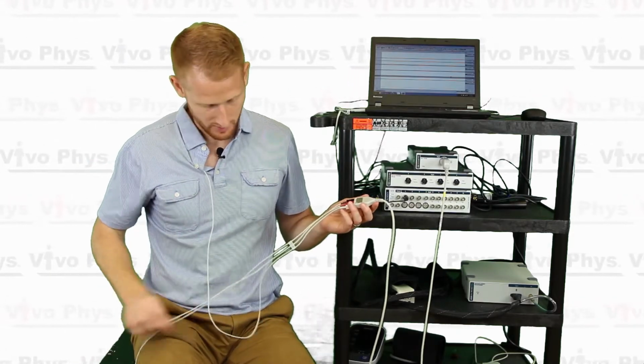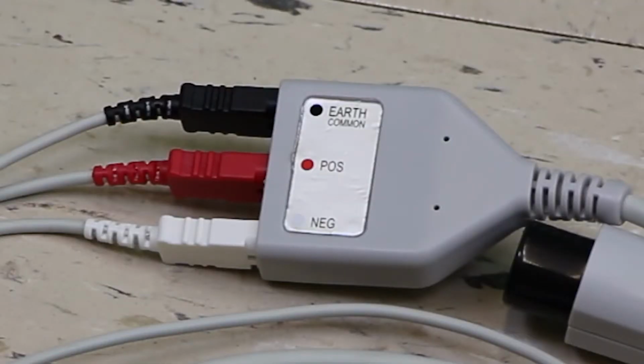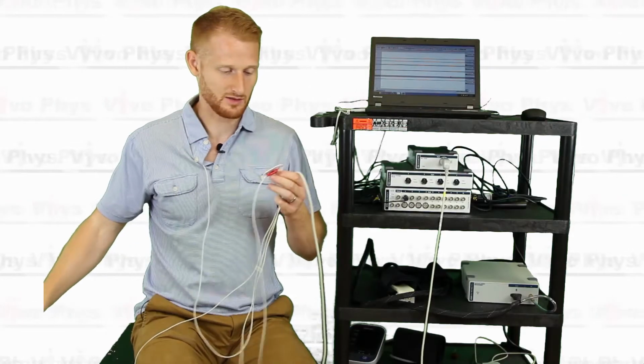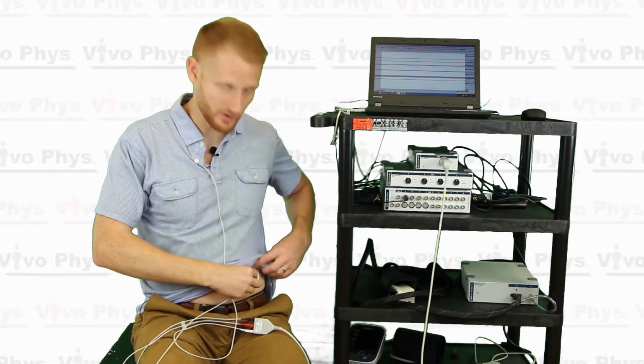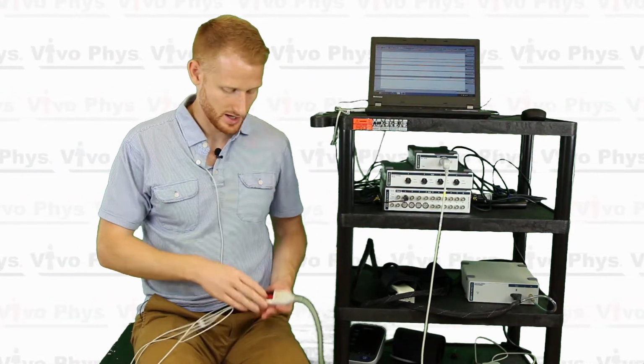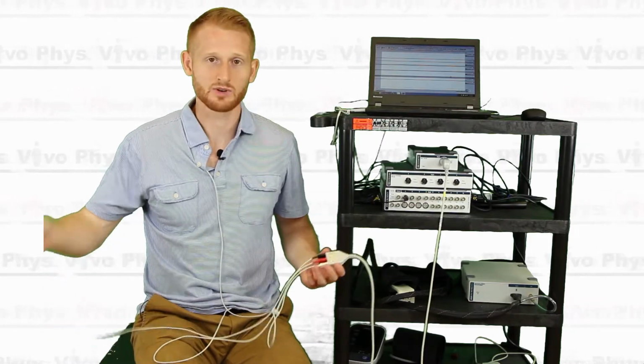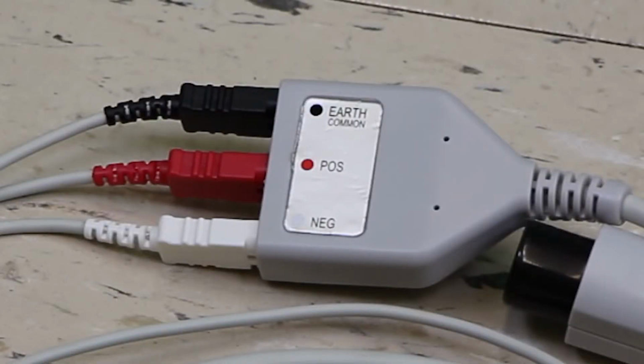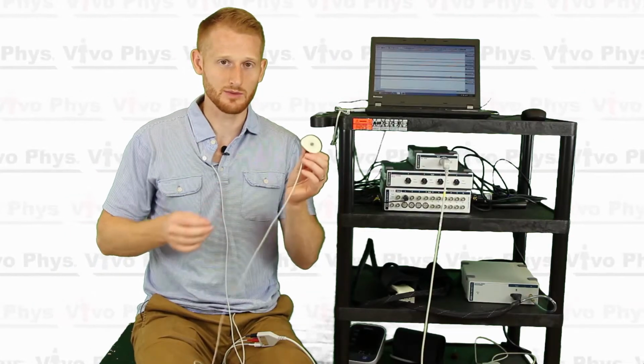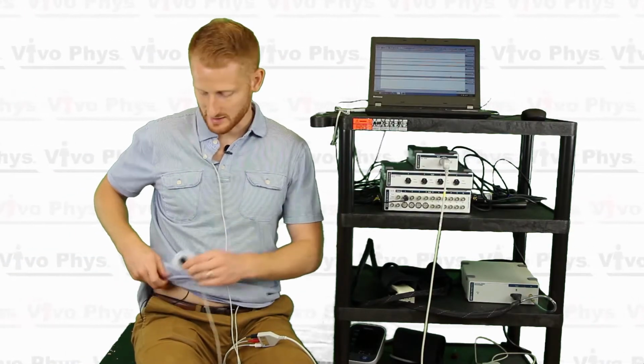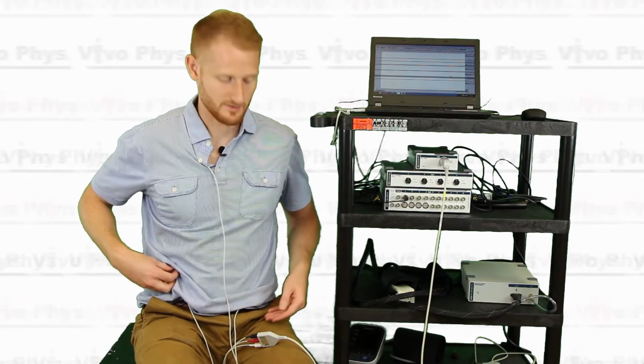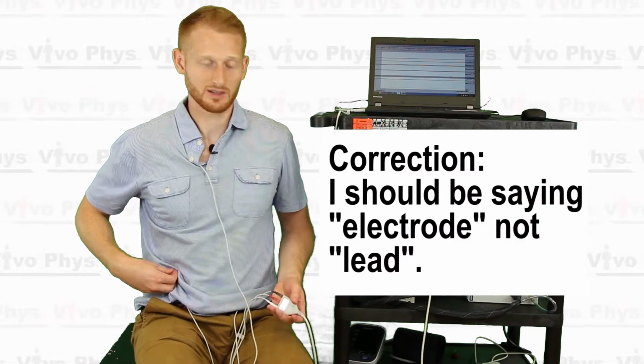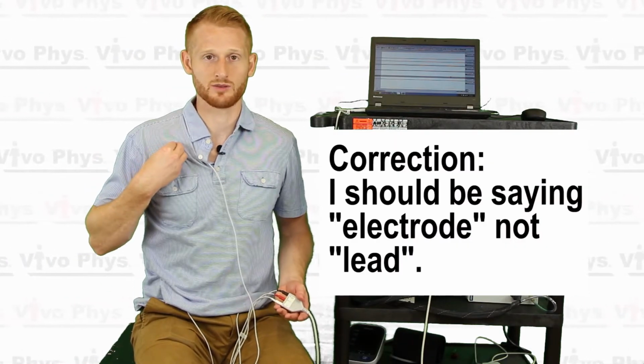The next one here is going to be the positive electrode. Same thing, peel off the back of the sticker. This one's going to go on my lower left-hand side, so I'm going to put it right there on my stomach. And then the last one here, which is the ground or the earth electrode, is typically placed on your lower right-hand side, toward the leg electrode. So this is the right leg electrode, the left leg electrode, and the right arm electrode.